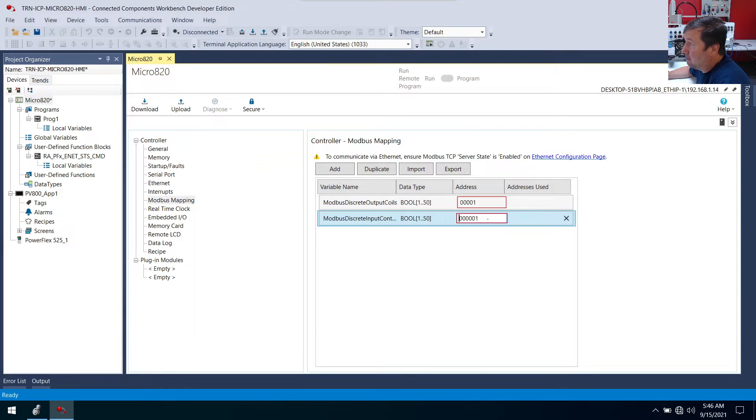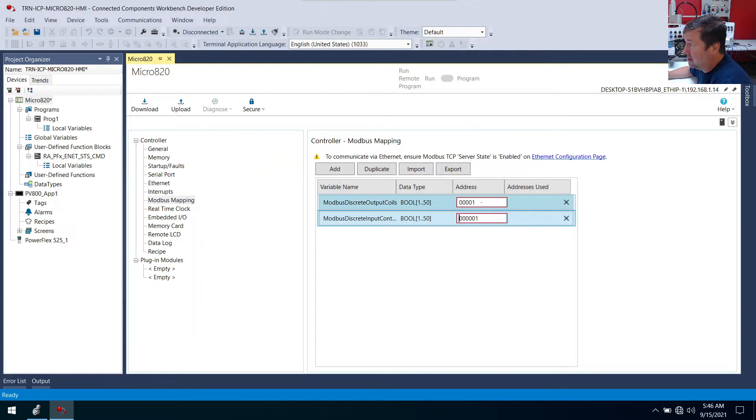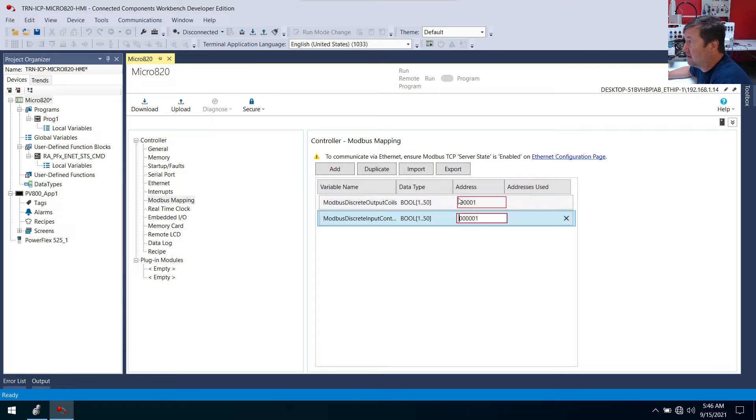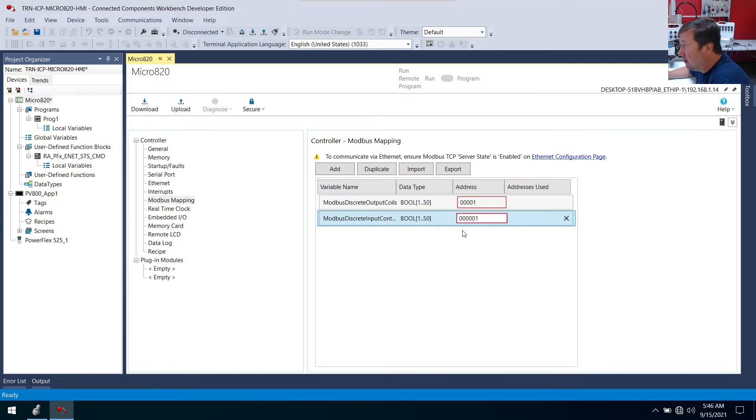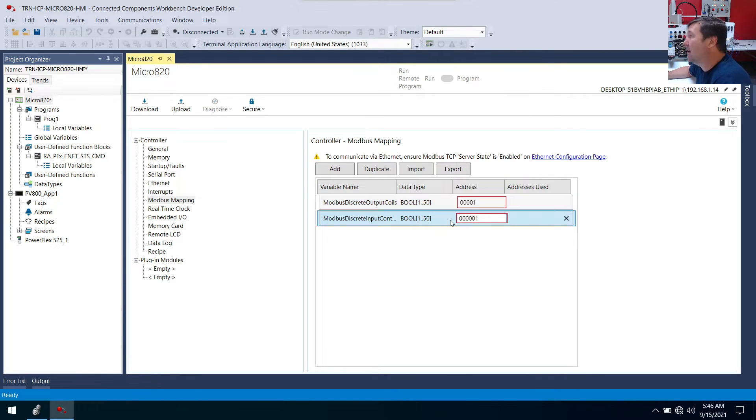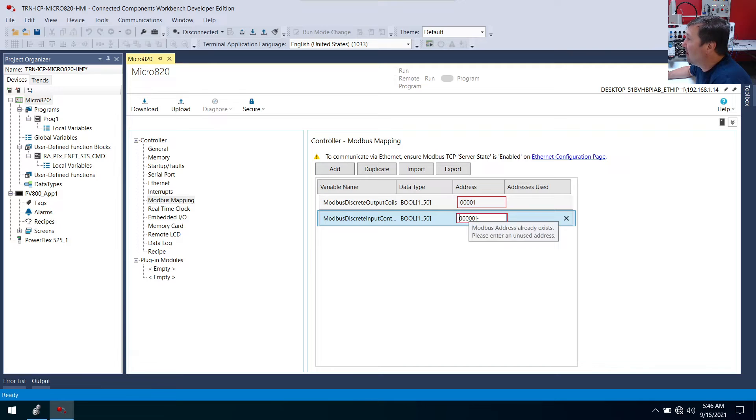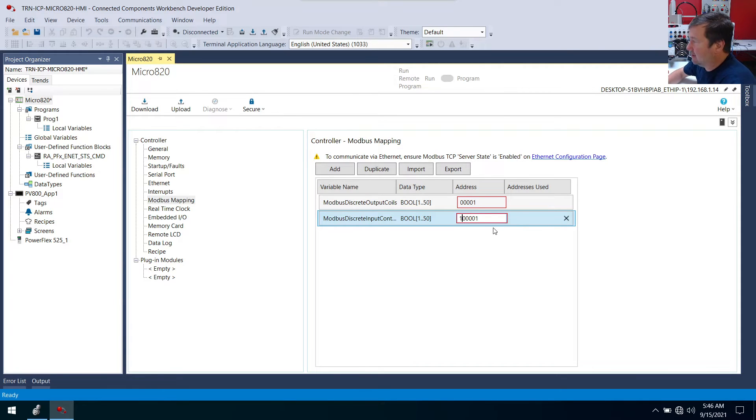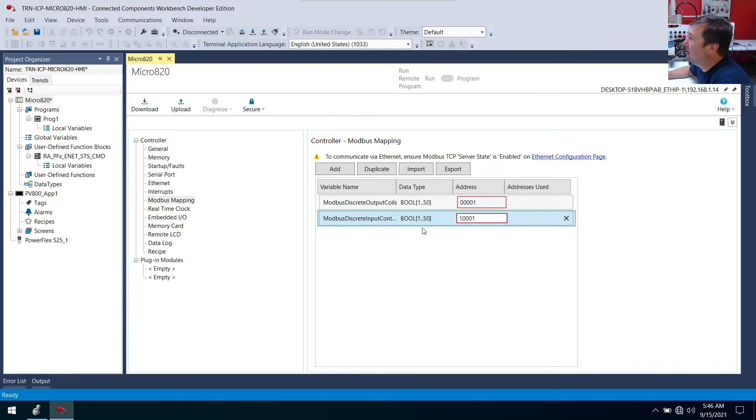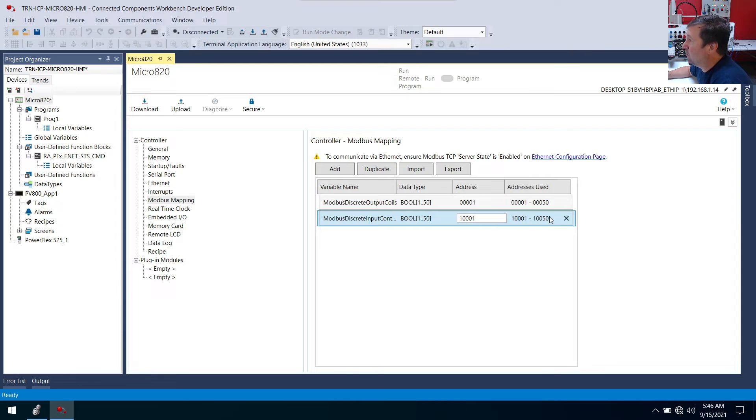And by default, it's actually going to end up back at that same number because there is a difference between 00001 and 000001. So in this case, usually your input contacts are going to be actually on 10,000. So I'm going to put a 1 in front of that. And then we're going to get one of those decimals out again. So I'm going to put this on 10,001. So it's going to be 10,001 through 10,050.